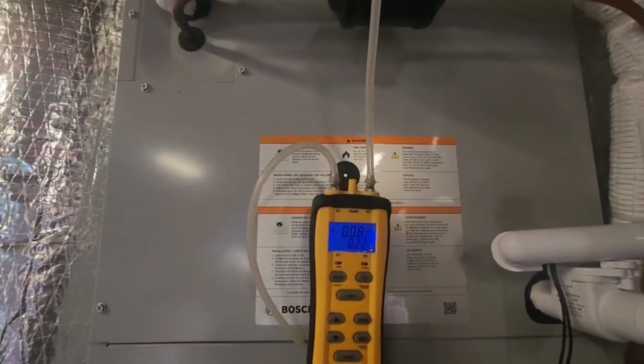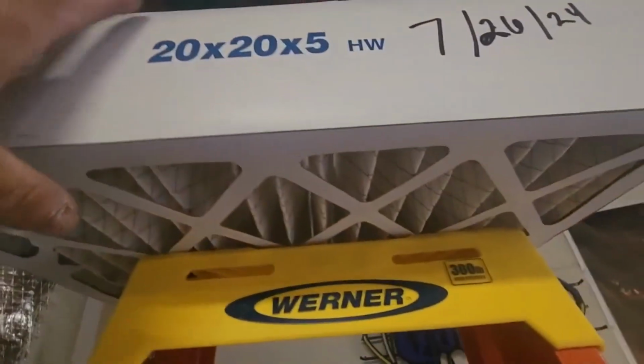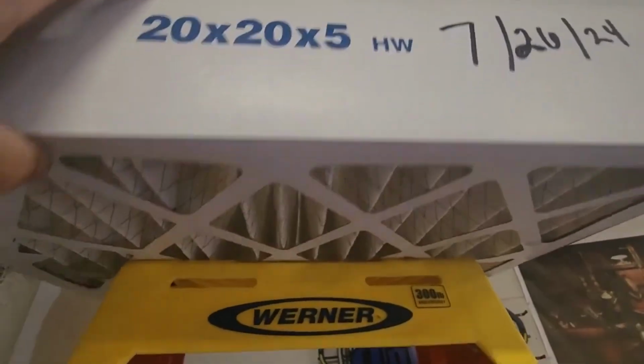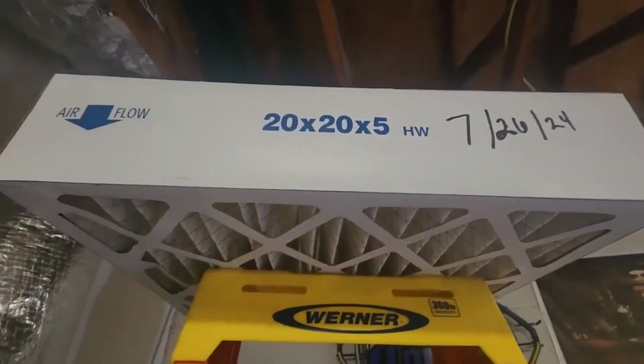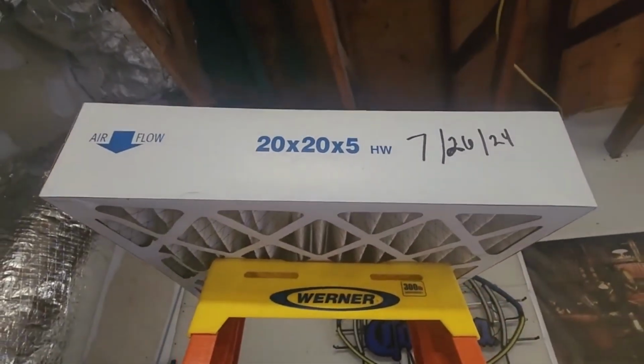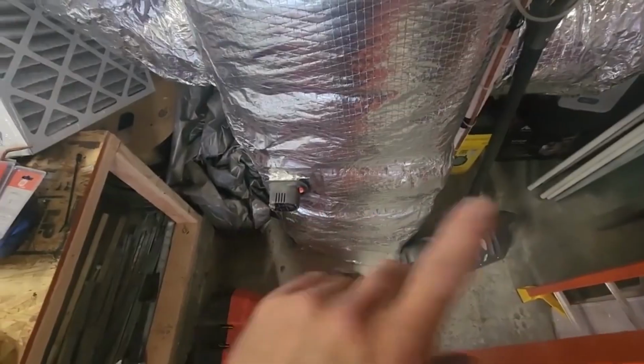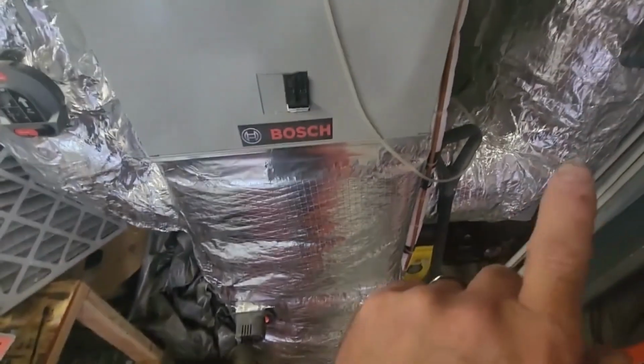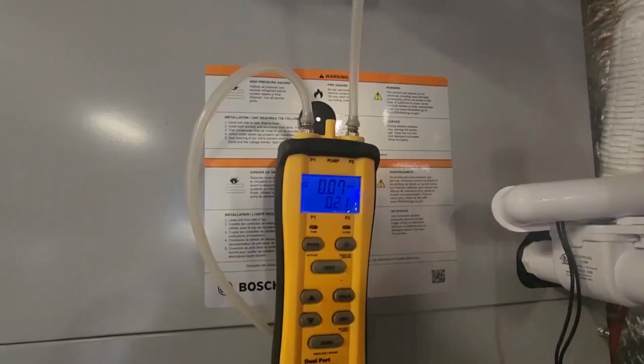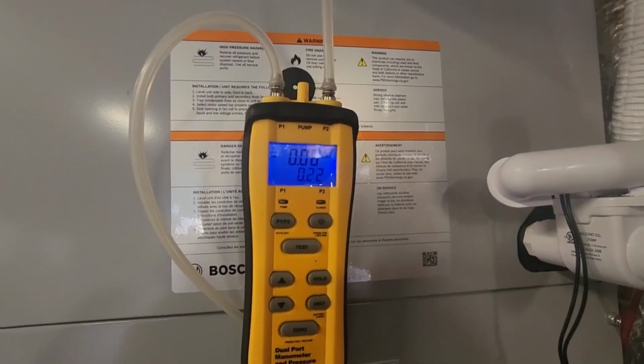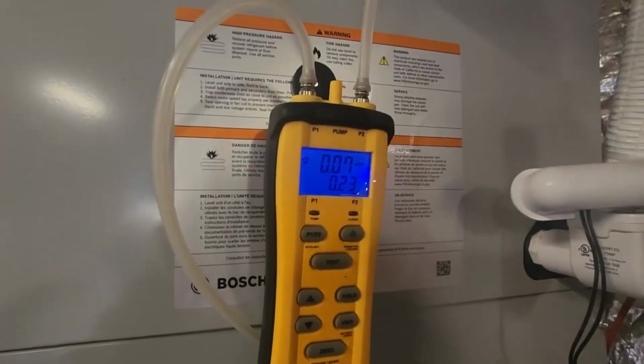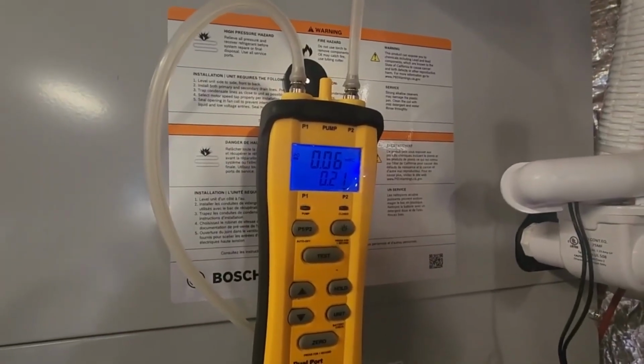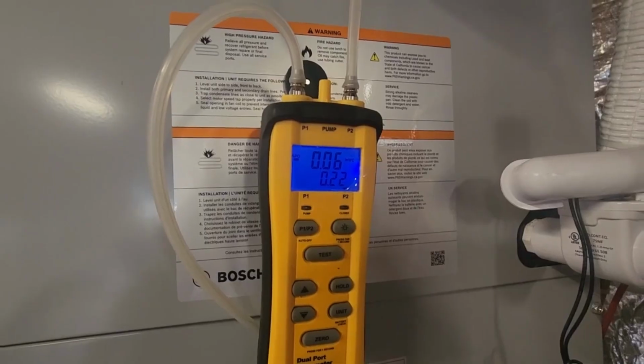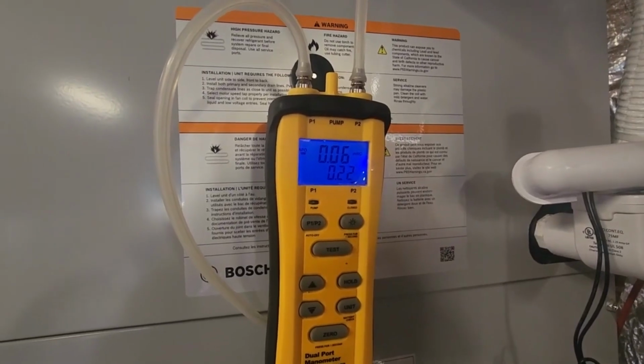So that's awesome. That's a filter I just put in the other day, and it's clean. It gives you less than 0.1 static on first stage. That is awesome. So right now we're still just running the downstairs. Let's flip them and see what we got without the filter in, with just the upstairs going. Okay, I have just the upstairs going now. So I guess these zones are ducted pretty similar static wise, as far as their total external static pressure.